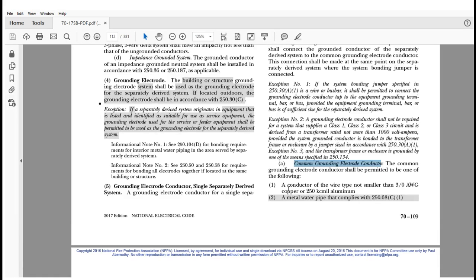Now, in the 2014 code, when we say common grounding electrode conductor, we understand that if we have multiple separately derived systems, in the past we could run a single conductor, size not smaller than 3/0 copper or 250 kcmil aluminum, and then we could have connections, taps if you will, to that common grounding electrode conductor. Now that was pretty common. We saw that in high rises to facilitate the connection of multiple separately derived systems.